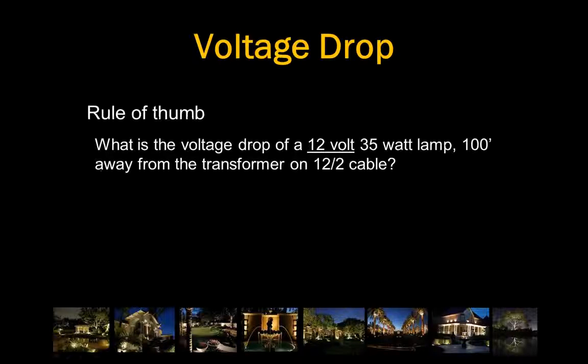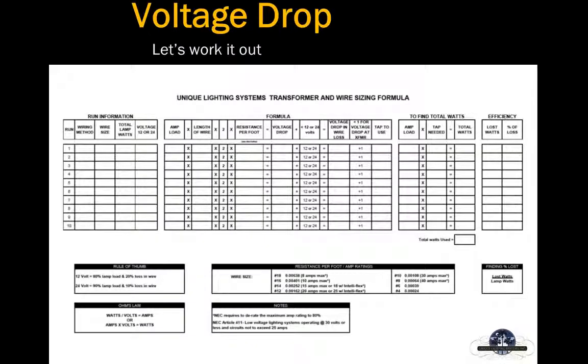I get this question all the time in varying different areas, but to make this for this class, what is the voltage drop of a 12-volt, 35-watt lamp that's 100 feet away from the transformer? Well, let's go ahead and work it out.